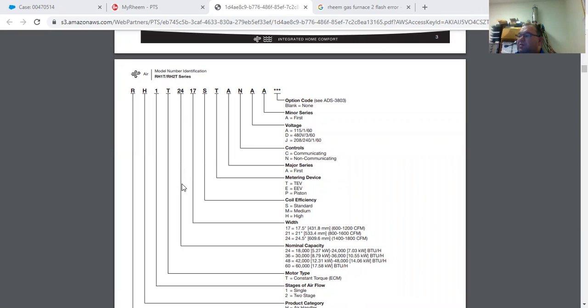Comes in whole capacity, so you have 2-ton, 3-ton, 4-ton, and 5-ton. In this case here, it's a 24,000. It's a 2-ton. We have 3 standard widths, which is 17.5, 21, and 24. Depending on the unit, there's 3 different efficiencies. You have a standard, the S, an M, which is the medium efficiency, and an H, which is the high efficiency. The T here stands for TXV, TEV. You also have an E for an EEV, and you have a P for a piston.